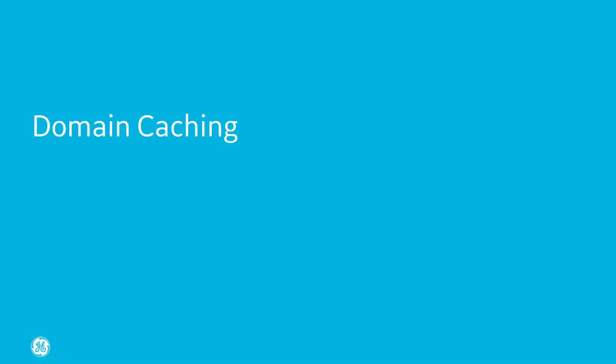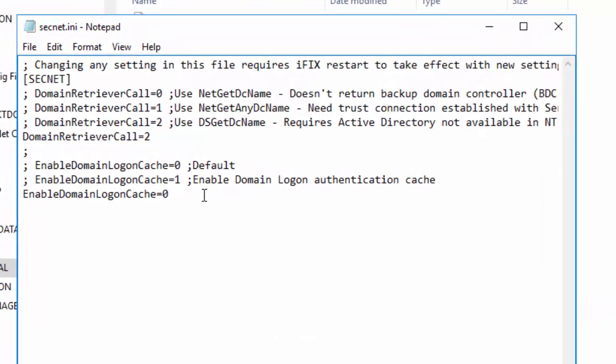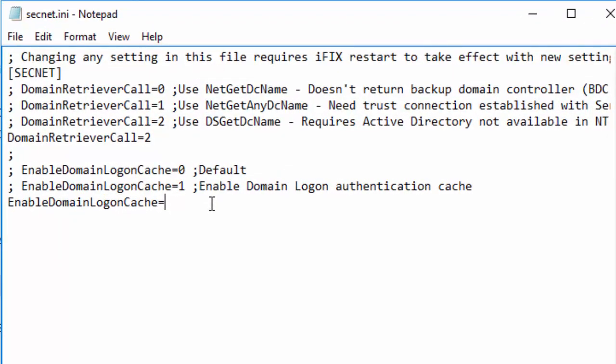Domain caching. iFix 6.0 supports multiple domains and domain caching. Enable domain caching in the secnet.ini file located in the iFix local folder. So basically, you're just going to change this setting to 1 to enable it, and then save the file and restart iFix. And be sure that other security countermeasures are also enforced, such as strong passwords.